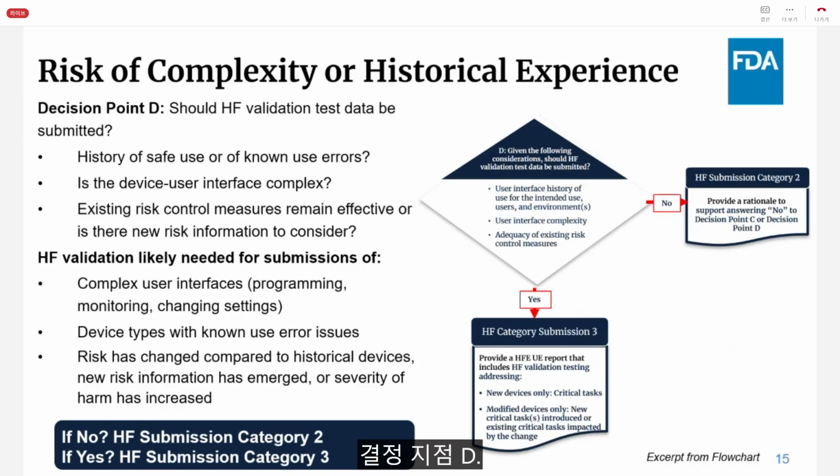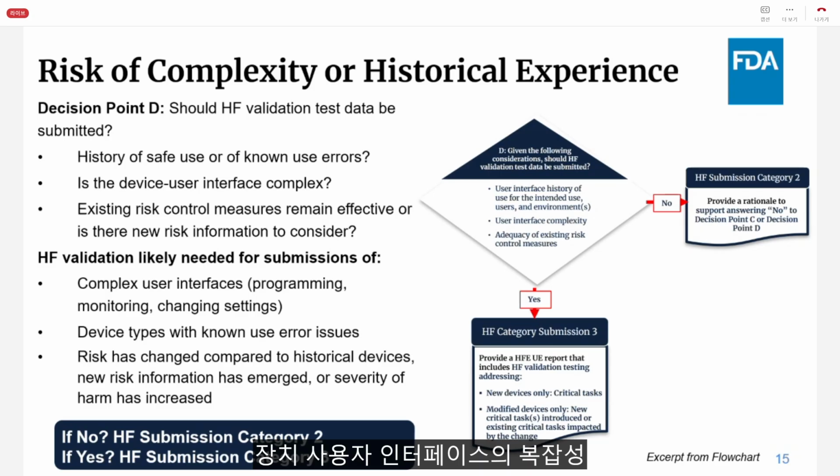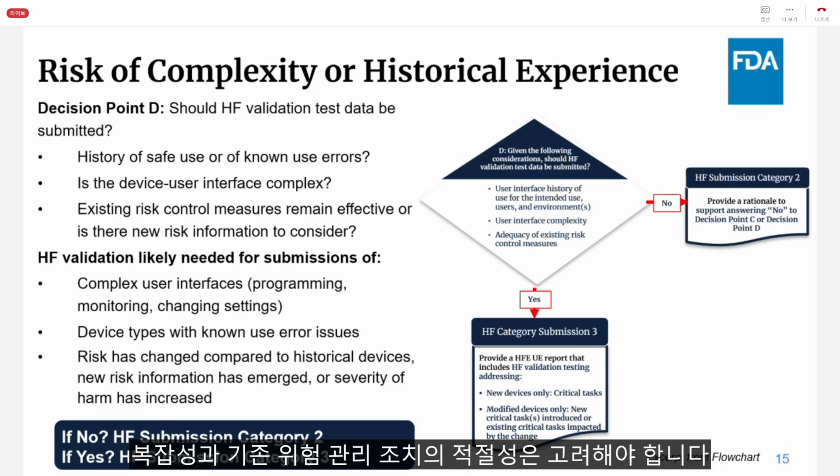Decision point D. Given considerations related to the history of the user interface for the intended use, users, and use environments, the complexity of the device user interface, and the adequacy of existing risk control measures, should new human factors validation testing be submitted to FDA?